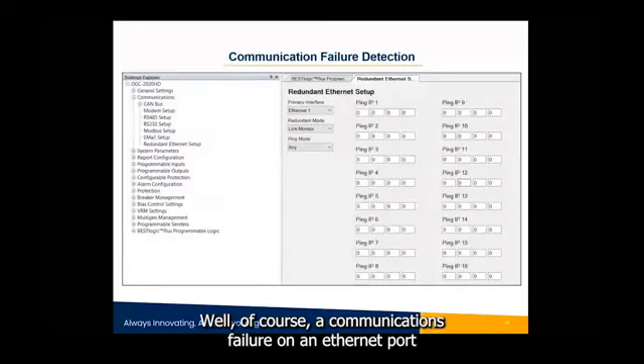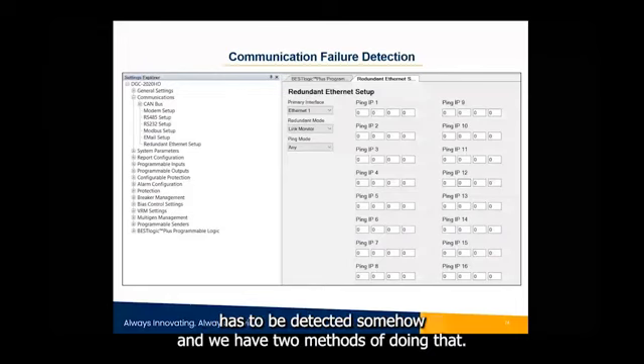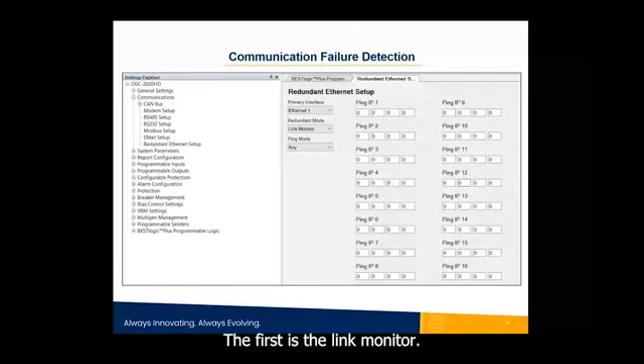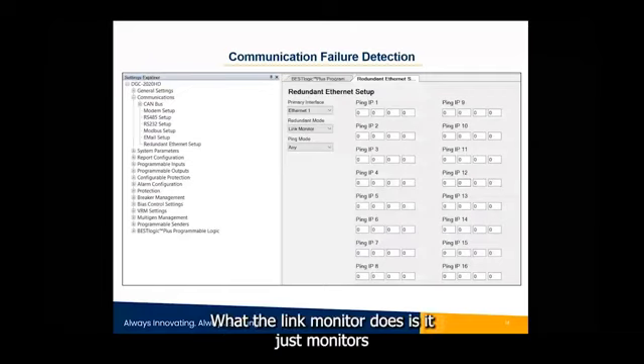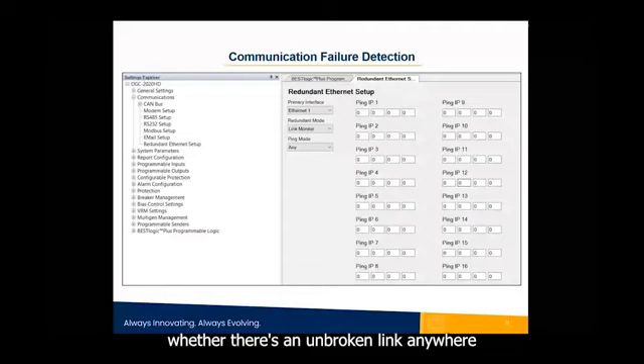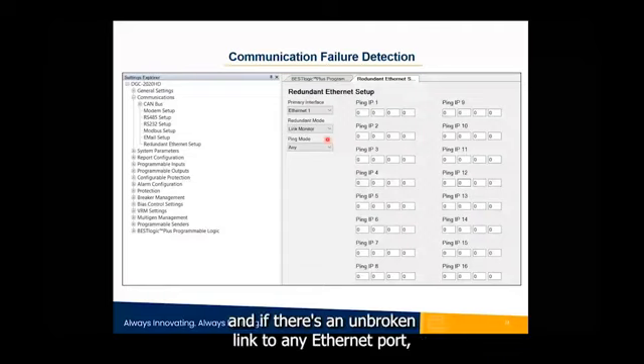Well, of course, a communications failure on an Ethernet port has to be detected somehow, and we have two methods of doing that. The first is the link monitor. What the link monitor does is it just monitors whether there's an unbroken link anywhere, and if there's a broken link to any Ethernet port, then it's going to determine that a comms failure has occurred, and it's going to enunciate that as a pre-alarm.